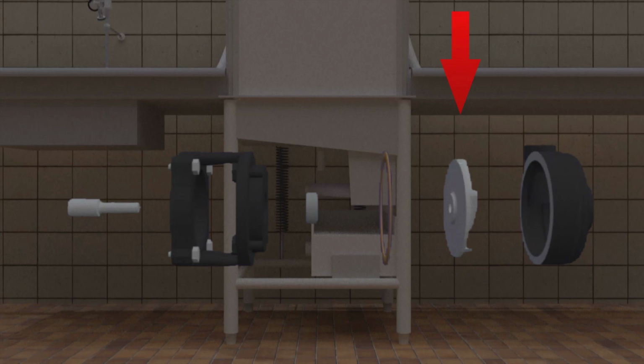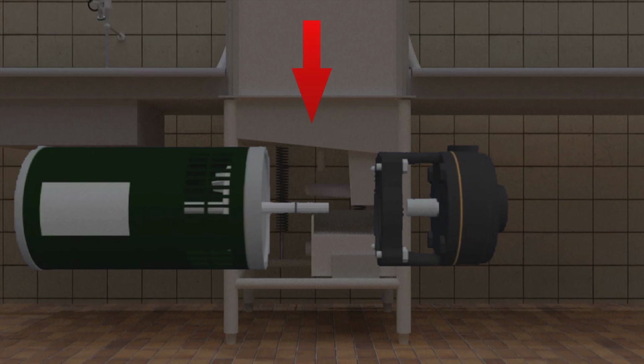Inside the pump is the impeller, which is attached to a metal rod called a short shaft. The short shaft passes through a pump seal and connects to the motor shaft. Also on the motor shaft is a rubber washer called a slinger. This washer prevents water from traveling into the motor in case the seal should ever leak. The motor connects to the pump with 4 bolts from the base, allowing room for the motor's shaft. This shaft protrudes from the body and spins at 3,450 revolutions per minute.